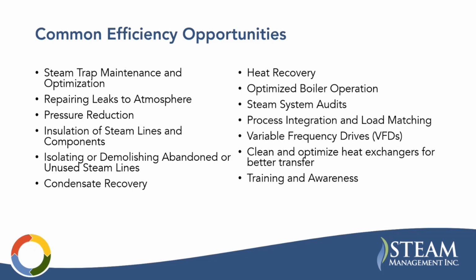So having your boiler run full out for periods of the day, and then having it run below its minimum capacity, that can be a lot of waste. If your steam demand is lower than your boiler's lowest operating point, your boiler is going to short cycle. And every time it cycles, it has to purge air through the boiler, and that's just wasted heat, just air cooling down the boiler for no real use of that heat. So that's to be avoided. So you can get a lot of energy savings just by integrating your processes with your boiler capacities and run times. Variable frequency drives on pumps and fans in the steam system is a good opportunity.